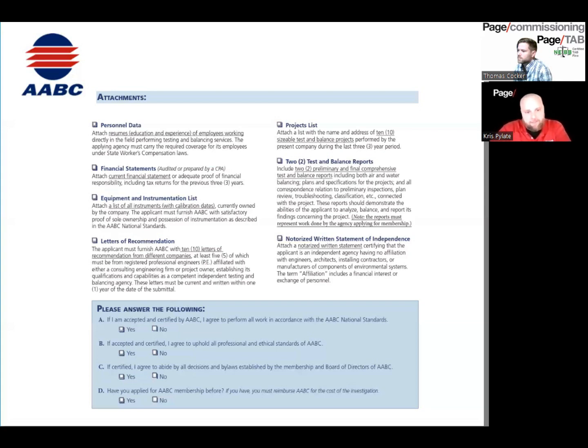For equipment and instrumentation, they want to see that you've purchased $6,000 to $10,000 worth of equipment and had it calibrated — before you even have certified jobs to pay for it. NEBB has the same requirement. In terms of recalibration, both AABC and NEBB require once-a-year recalibration with NIST calibration and three-point verification, so they're pretty similar in that standard. When the equipment was purchased, it was close to $20,000.